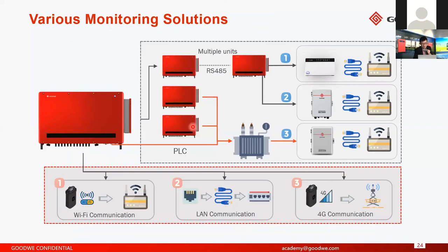And for our MT series and also HT series, we can support various monitoring solutions. We can support Wi-Fi communication, LAN communication, and also 4G. 4G communication is on the way, and I think it should be released in July. For big plants, we also have RS485 communication. With RS485, you can use our data logger, the EasyLog Pro, and also connect multiple units to our SEC 1000. The SEC 1000 is not only for monitoring, you can also do export power limit, and as just mentioned, reactive power compensation.